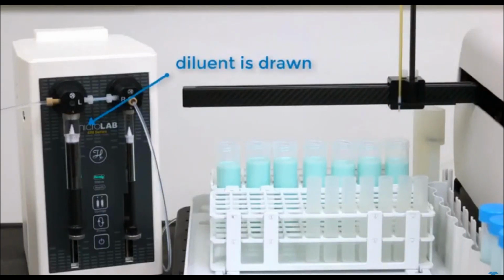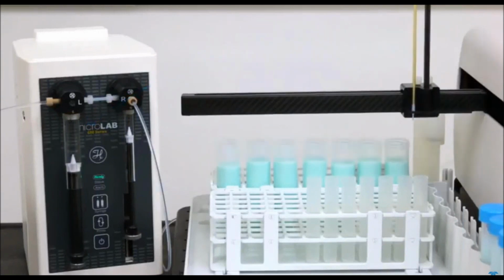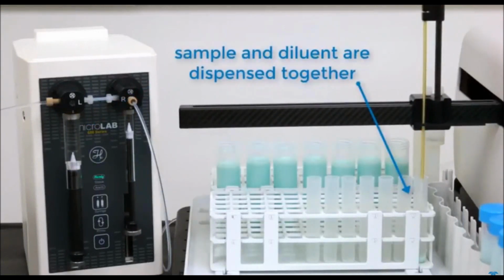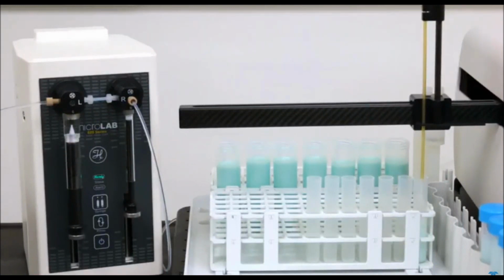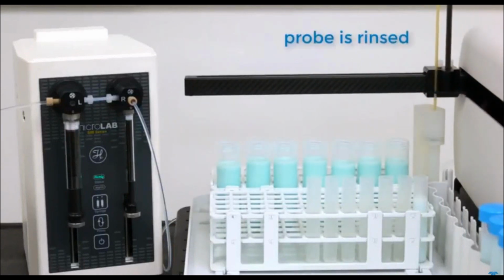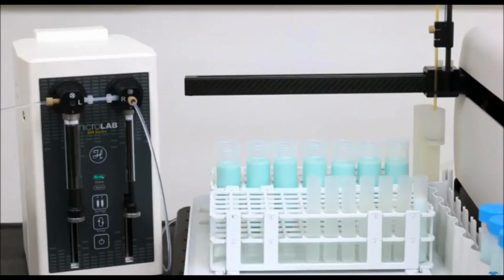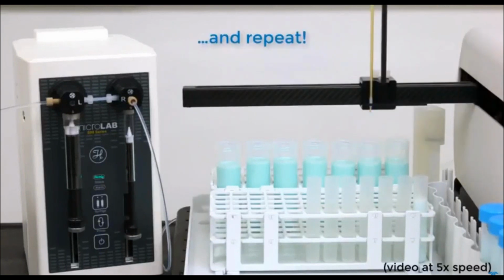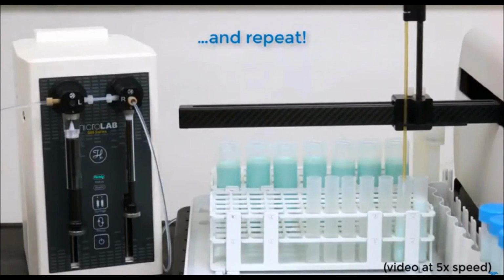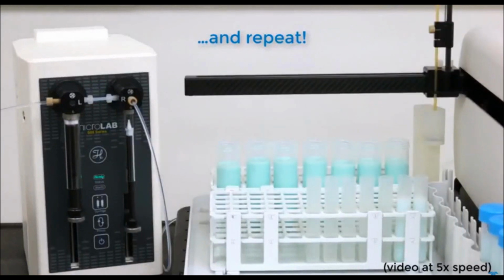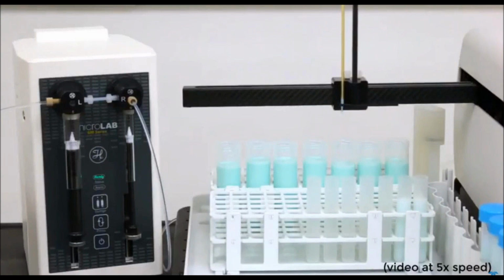Sample is pulled up, the diluent is drawn. One of the really nice features of the Microlab system from Hamilton is it does have the dual syringes, which allows you to handle large volumes, but also have the accuracy of smaller syringes. And Hamilton is able to provide us with syringes ranging from 50 milliliters all the way down to 10 microliters. So after it dispenses, the probe is rinsed. Again, that's user configurable, so it's up to the lab to program that as they will. And repeat.